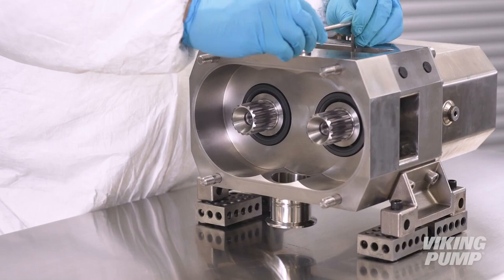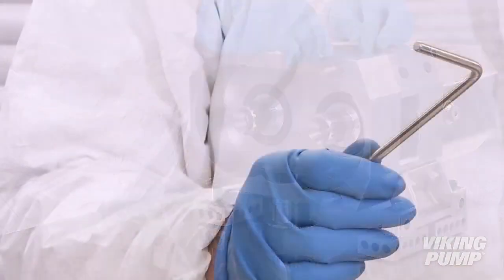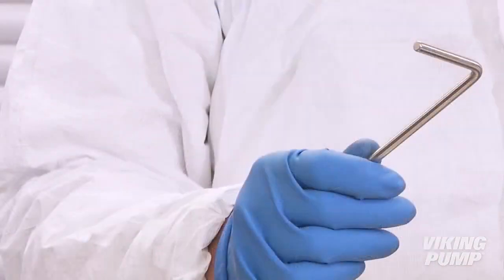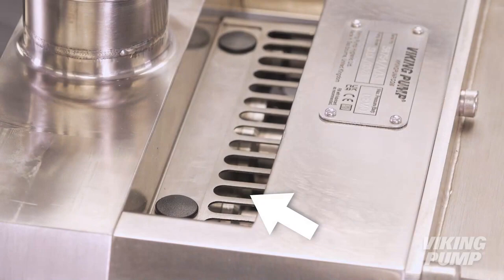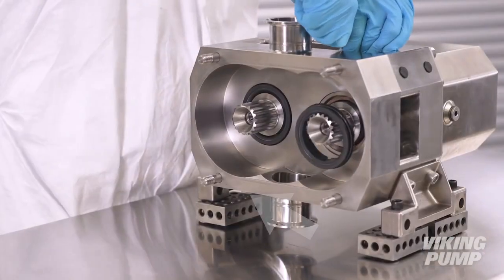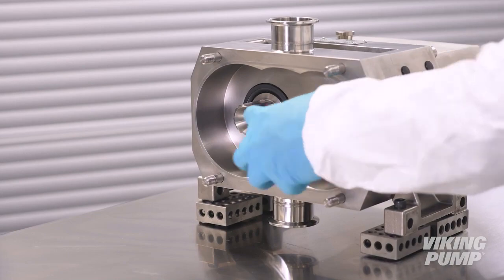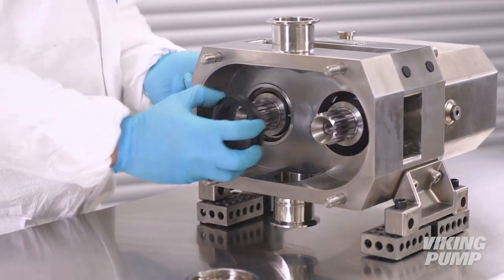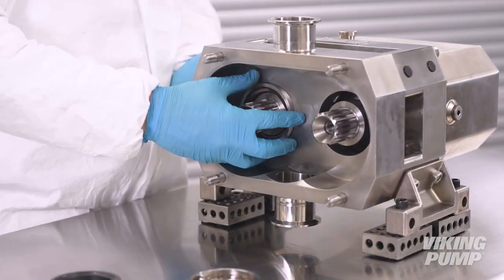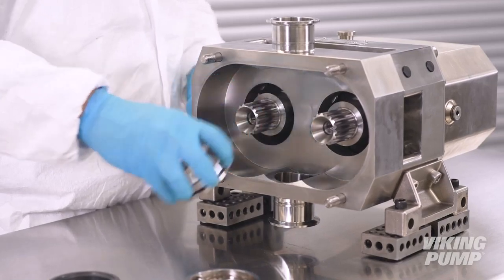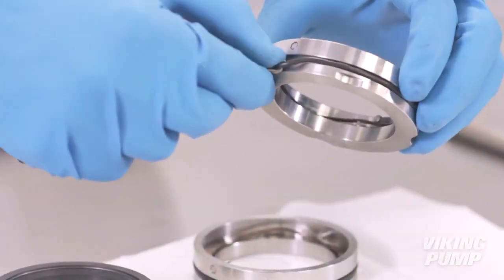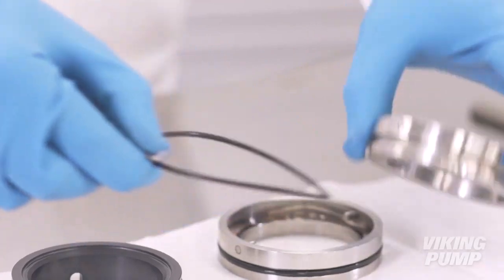Remove the stationary seal assemblies from the rotor case by inserting the provided seal removal tool through the guard and pushing on the back of the seal to push each out of the rotor case bore. Remove and discard the seal housing O-ring and wave spring.